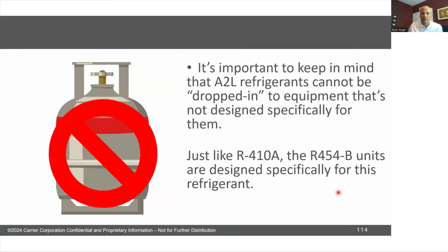If it wasn't obvious, the A2L refrigerants, 454B and R-32, are not direct drop-ins for 410A. You could probably put it in there. It probably would sort of kind of work for a while, but what things would break, I don't know. And then you also would have the liability when something went wrong. And maybe it would be fine for 99 out of 100 jobs, and then there's that one job where something goes wrong, and then you're in trouble. So just don't do it.